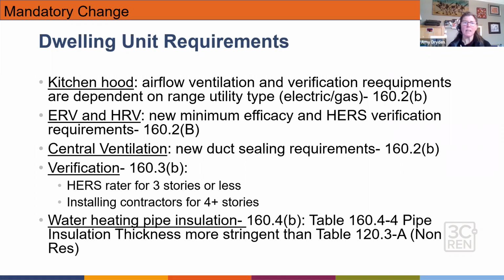Next slide. Dwelling unit requirements. So that kitchen hood table that we were looking at before also applies to dwelling units in multifamily. We just didn't repeat the slide here. And it's an important element in terms of those square footages, because we do have smaller apartments, and we want to make sure that the flow rate is reasonable for the conditioned floor area and not too much, but really effective, so we can remove those pollutants in those homes.